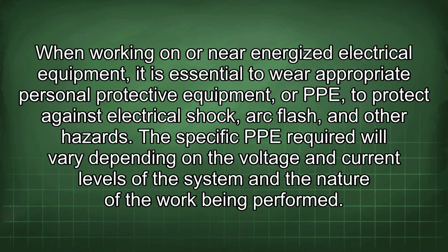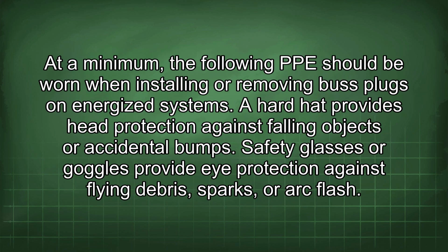When working on or near energized electrical equipment, it is essential to wear appropriate personal protective equipment, or PPE, to protect against electrical shock, arc flash, and other hazards. The specific PPE required will vary depending on the voltage and current levels of the system and the nature of the work being performed. At a minimum, the following PPE should be worn when installing or removing bus plugs on energized systems. A hard hat provides head protection against falling objects or accidental bumps.